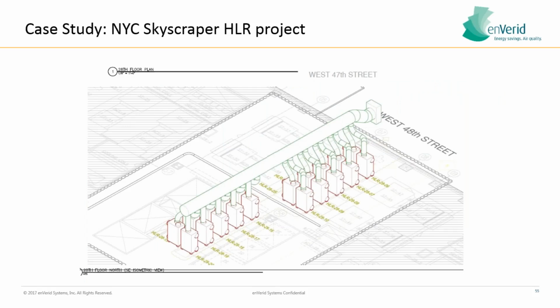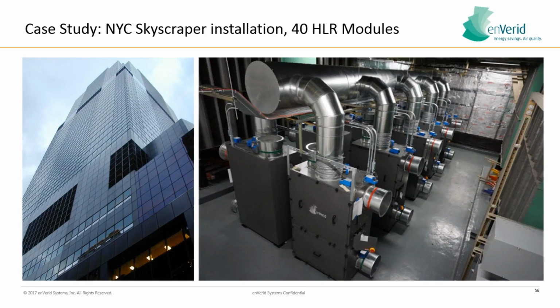And then you can get crazy with this as well, right? So brace yourselves. This is a 40-story, 1.3 million square foot application. This is the Morgan Stanley Worldwide Headquarters in Times Square, New York. 2 mechanical penthouses in this building, split into 2 sections each. So we had 10 HLRs here, 10 on the other side of the building. This mechanical room is an open air plenum. So it's a giant return, and unducted, we're drawing air into the units, returning that clean air back into that room, and then the fan wall is drawing that clean air back into the system.